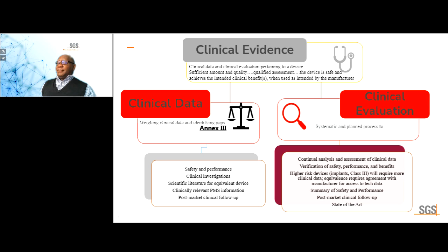But it's still possible. Then these 2 strands of evidence, or these 2 strands of data, then go into what we call clinical evidence. Data and clinical evaluation pertaining to a device. You need a sufficient amount and quality so that a qualified assessment can be made to determine if your device is safe and achieves the intended clinical benefits when used as intended by the manufacturer. Again, we're going back to the intended purpose as defined by the manufacturer.